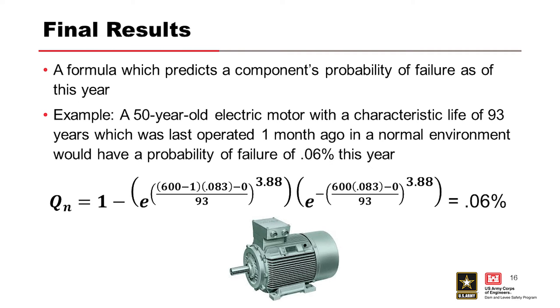The final results. So, using those parameters for this, our example motor, a 50-year-old electric motor with the characteristic life of 93 years, which was last operated one month ago in a normal environment would have a probability of failure of 0.06% this year.